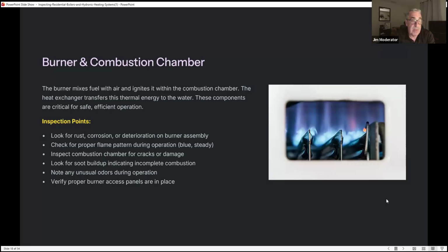So the inspection points: look for rust, corrosion, or deterioration on the burner assembly. Check for proper flame pattern during operation. You want to see a nice blue steady flame. No yellowing, no wavering, no gas too much. You want it to be very steady. Inspect the combustion chamber for cracks or damage.